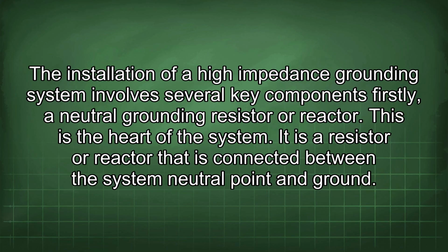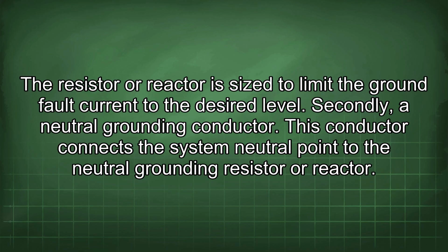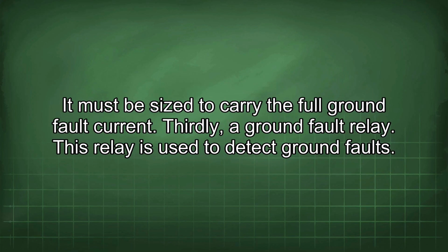The installation of a high-impedance grounding system involves several key components. Firstly, a neutral grounding resistor or reactor. This is the heart of the system. It is a resistor or reactor that is connected between the system neutral point and ground. The resistor or reactor is sized to limit the ground fault current to the desired level. Secondly, a neutral grounding conductor. This conductor connects the system neutral point to the neutral grounding resistor or reactor. It must be sized to carry the full ground fault current.